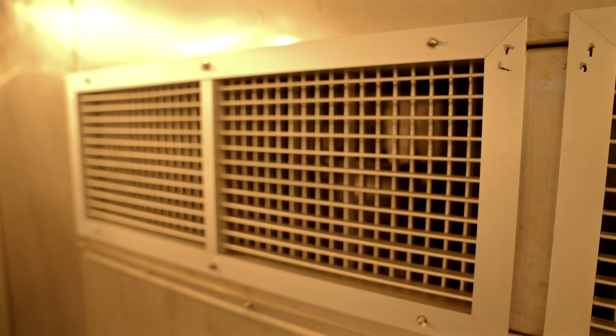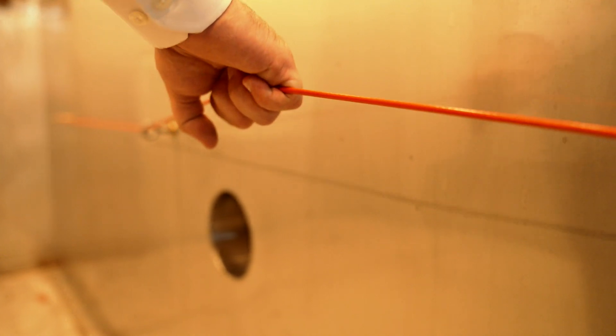Our solid construction chambers, like the one behind me, showcase our over 40 years of experience in building the most robust and reliable chambers of all. These chambers are designed with a fully-welded stainless steel interior to allow for extreme temperature and humidity testing.